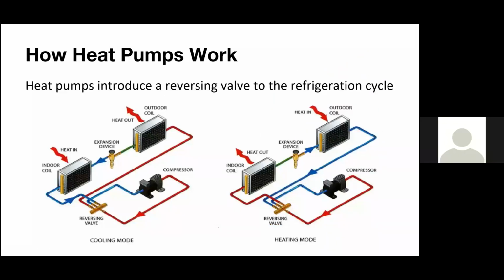So what you're looking at here, one thing to remember is that compressors only work in one direction, from the suction gas coming in to the discharge gas coming out. So if we want to reverse that cycle and start going the other way, we don't just run the compressors backwards. Similar to a car engine, they always run the same way. If you want to go in reverse, we use a gearbox to switch to reverse, but the engine is always typically spinning in the same way. This is what we do here via the reversing valve, which works as that gearbox. So it can determine in which direction the heat is going.